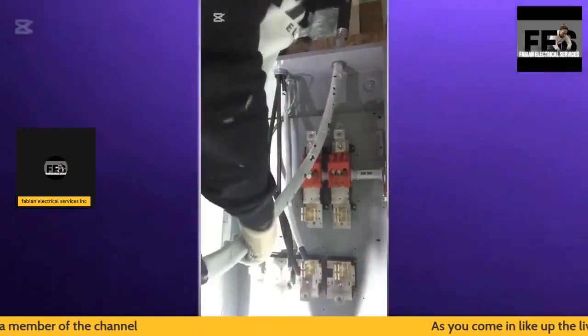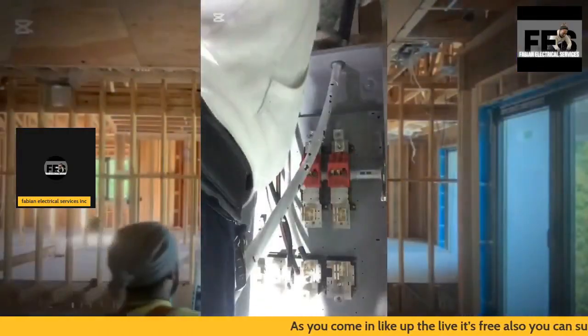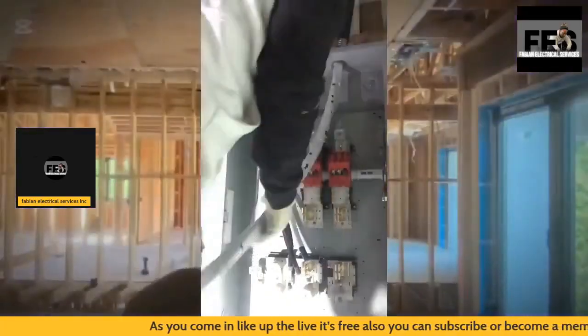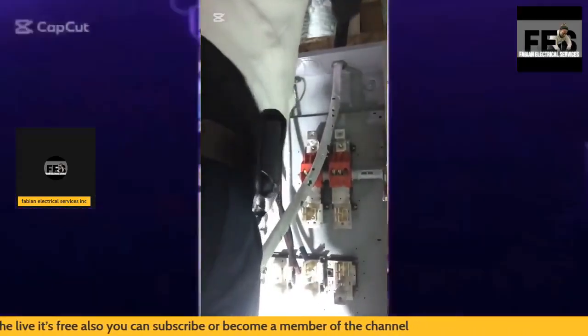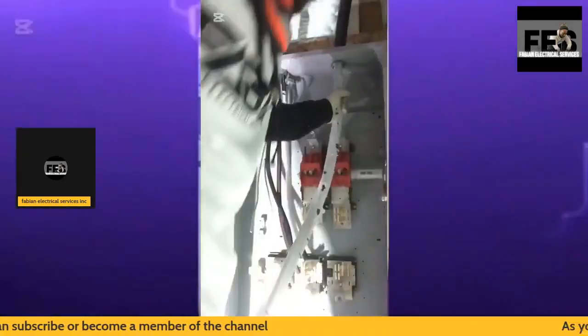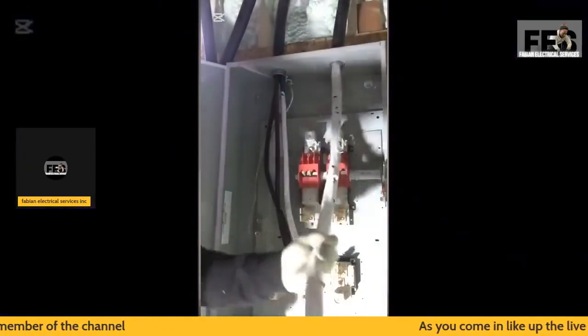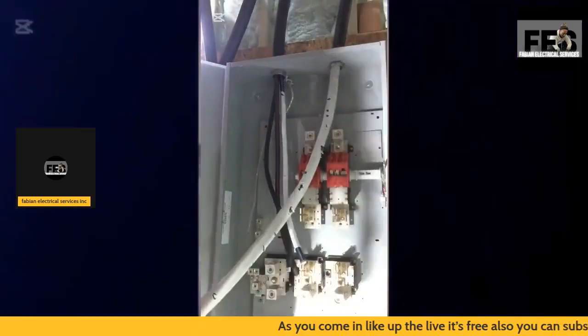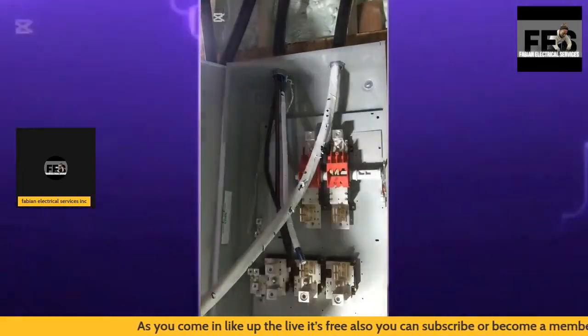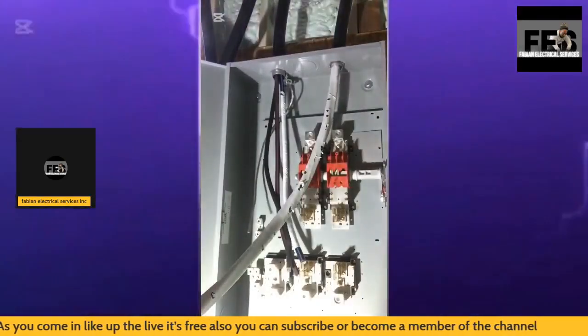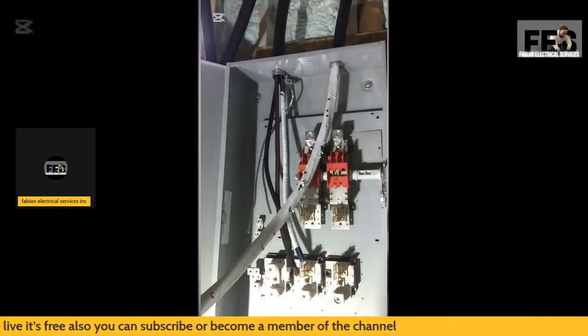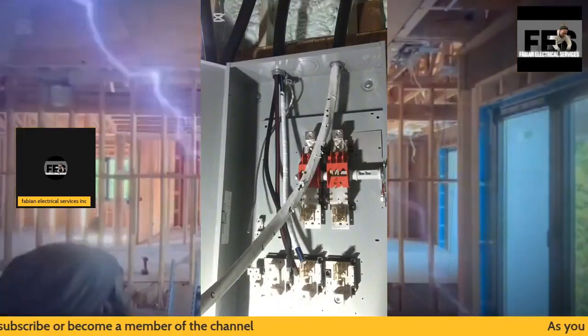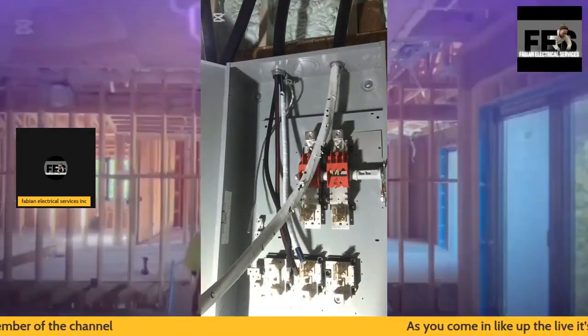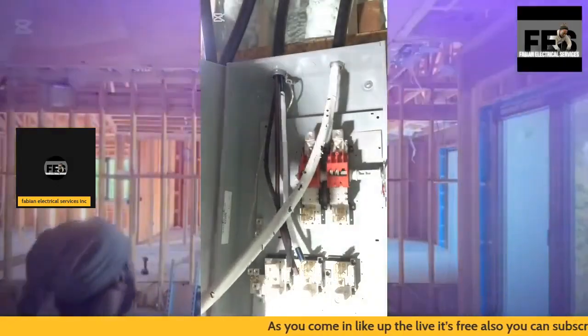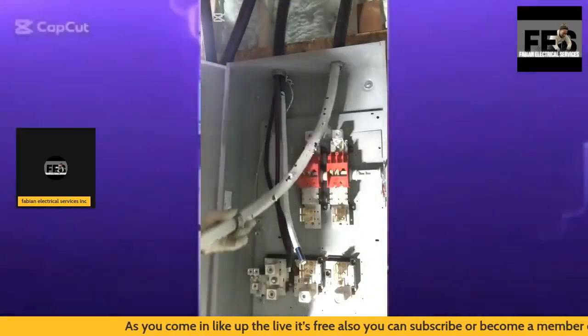Again, the cable I'm using is going to be the AC conductor. We call it TECK cable, and there are parallel runs being run from the outdoor meter base. What I like to do with an installation like this is keep that white sheeting on. Once I land my conductors inside of the panel, I'm going to remove that white sheeting.